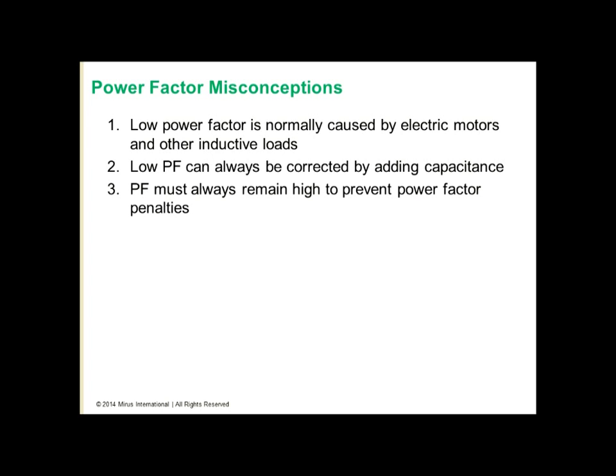Third is power factor must always remain high to prevent power factor penalties. In reality, although there are many different ways that power factor penalties are applied by utilities throughout the world, they almost universally apply these penalties during periods of peak demand. Therefore, if low power factor only occurs under lightly loaded conditions, it will not result in power factor penalties.